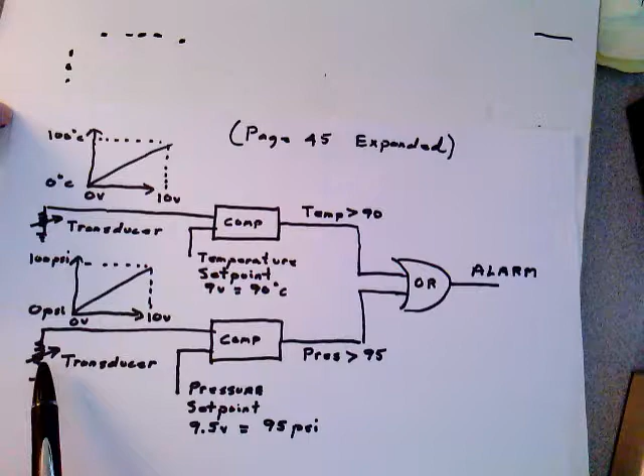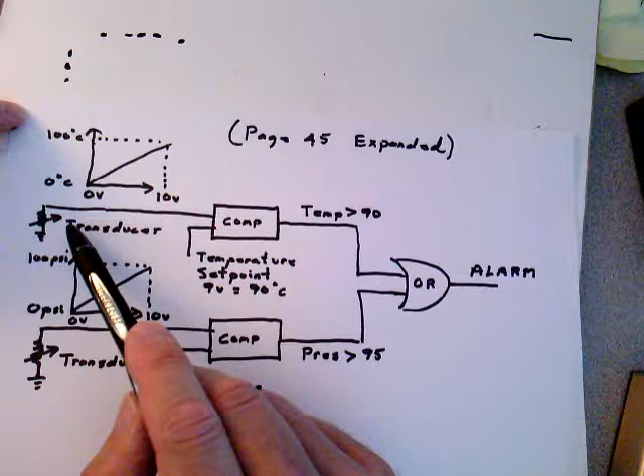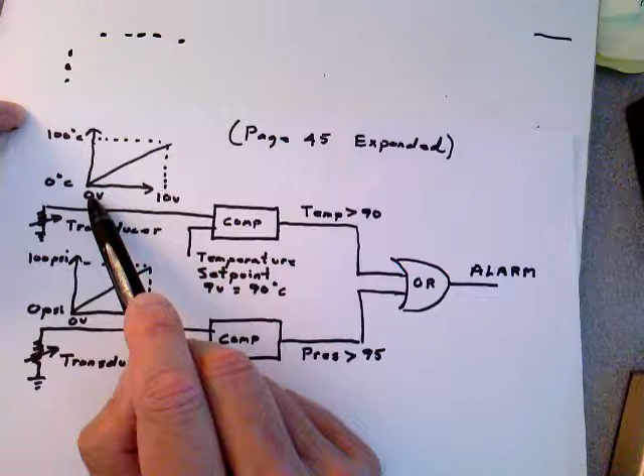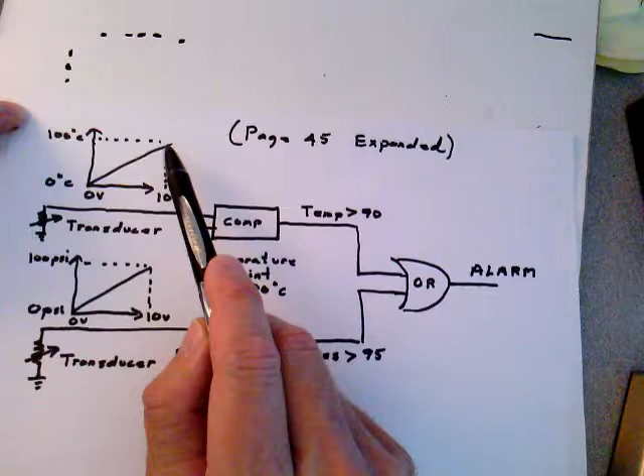Now, what does the output of the transducer look like? Most transducers are strain gauge devices that have a little bit of a nonlinearity to them, but it's real easy to make these linear devices. So basically, let's assume that the output of this temperature transducer goes from 0 degrees centigrade to 100 degrees centigrade, and it's linear between 0 and 10 volts. In other words, if you have 100 degrees C, you have 10 volts output here on this line. If you have 0 degrees C measured inside the tank or the pipe, you have 0 volts, and it's linear.